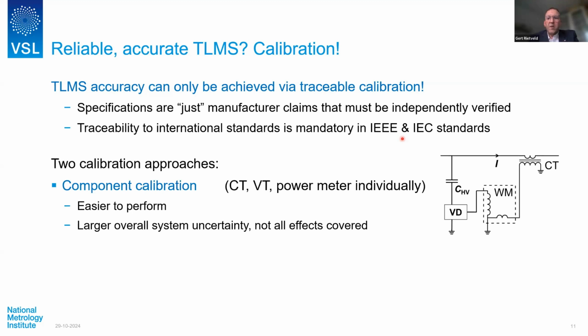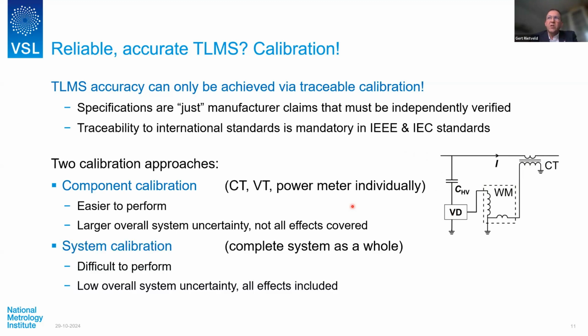And to calibrate a loss measurement system, there are two approaches. The first approach is component calibration. Here you have the voltage divider, the current transformer, and the wattmeter, so you can individually calibrate them and then add up the uncertainties to get an idea of the uncertainty of your total loss measurement system. It is relatively easy to perform, but the uncertainty evaluation is pretty complex, and also not all effects are covered. So that's why we moved to system calibration. Calibrate the system as a whole. It's more difficult to perform, but that's the challenge for the metrologist.